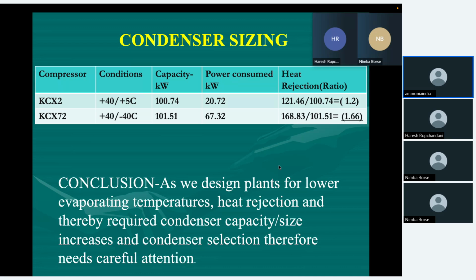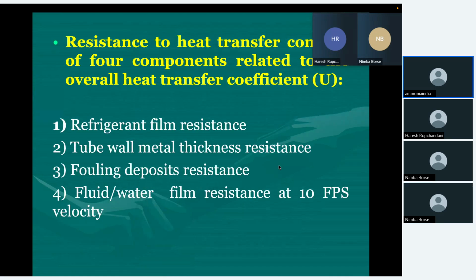But if you go to a lower temperature, you see the power consumption for the same capacity is as high as 67.32. So your ratio becomes 1.66. So the condenser should be designed 1.66 times bigger, that is for 168 kW capacity. Remember, this is a very, very important point. Many of the plants I have seen, people neglect this.